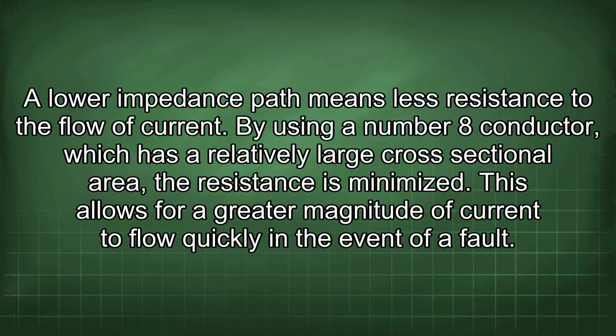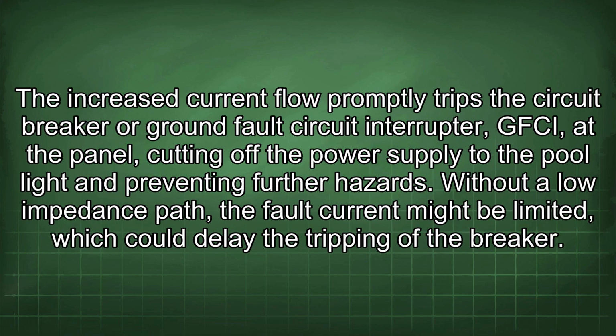A lower impedance path means less resistance to the flow of current. By using a number 8 conductor, which has a relatively large cross-sectional area, the resistance is minimized. This allows for a greater magnitude of current to flow quickly in the event of a fault. The increased current flow promptly trips the circuit breaker or ground fault circuit interrupter (GFCI) at the panel, cutting off the power supply to the pool light and preventing further hazards.